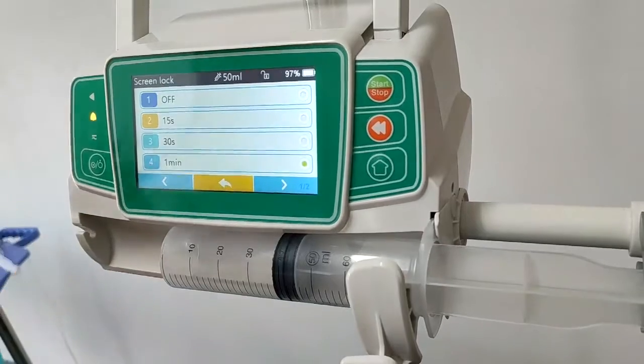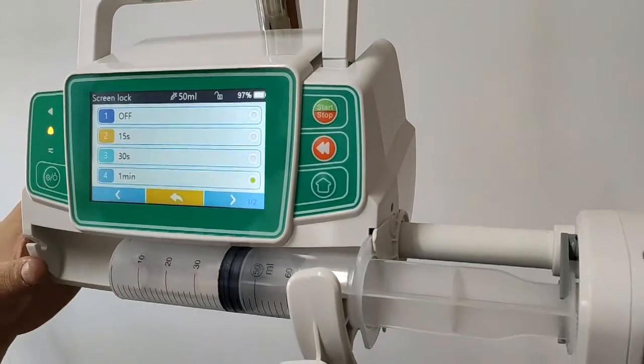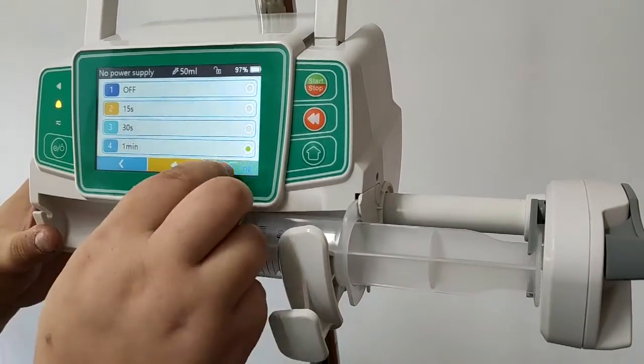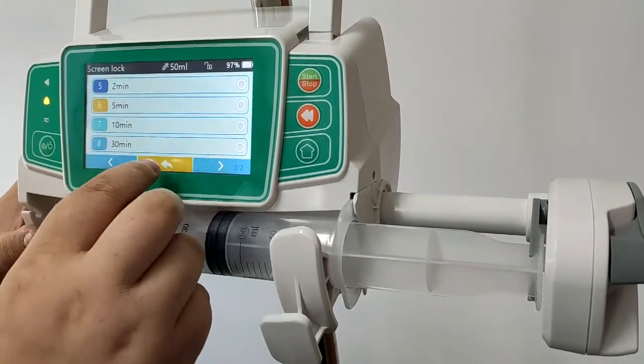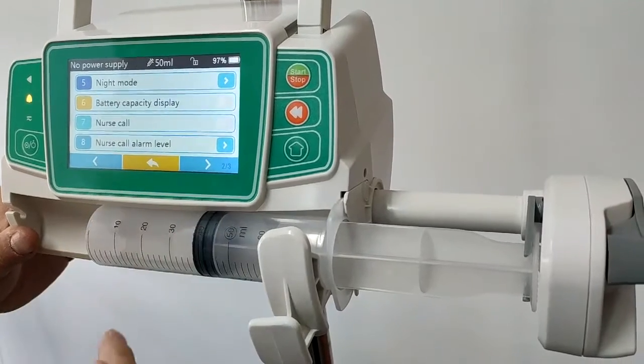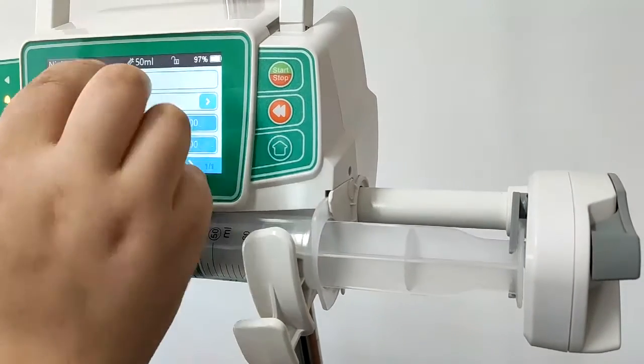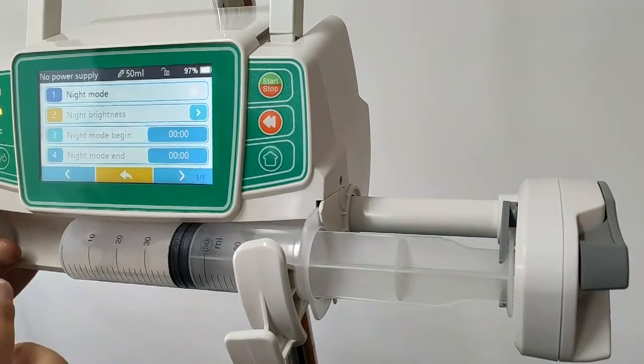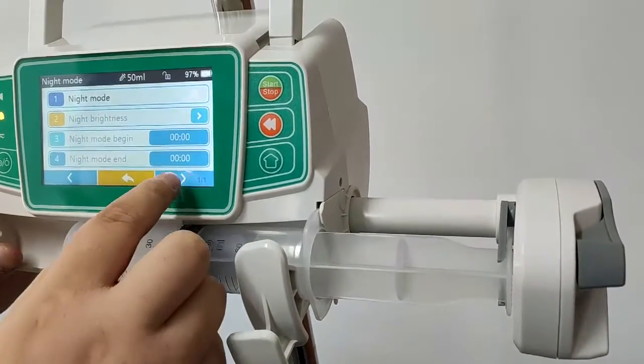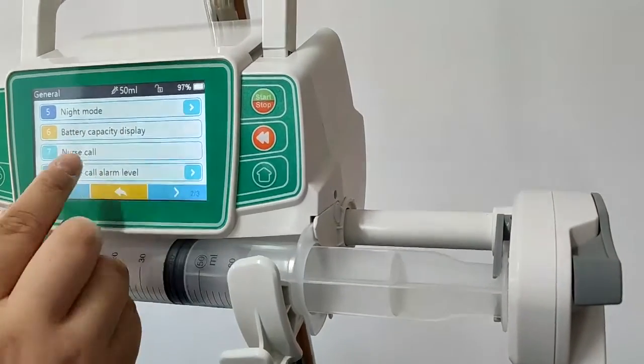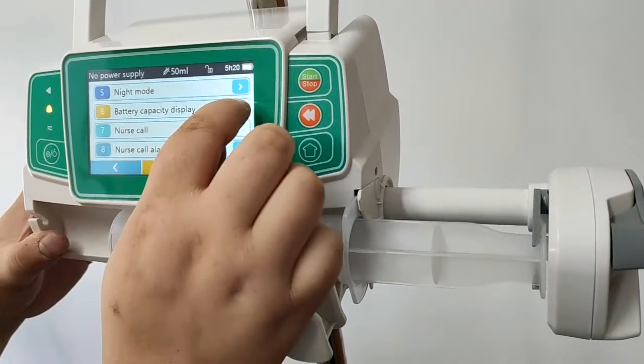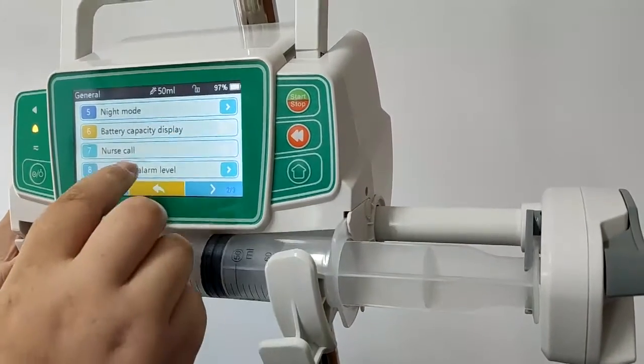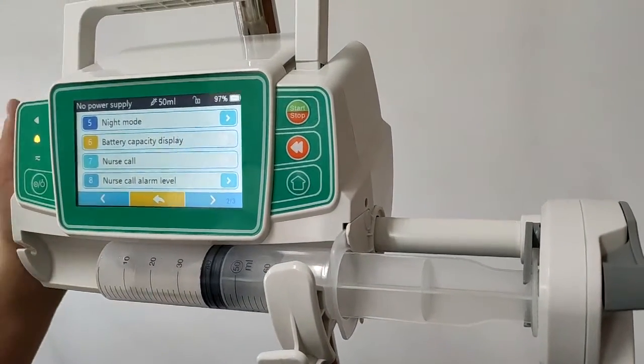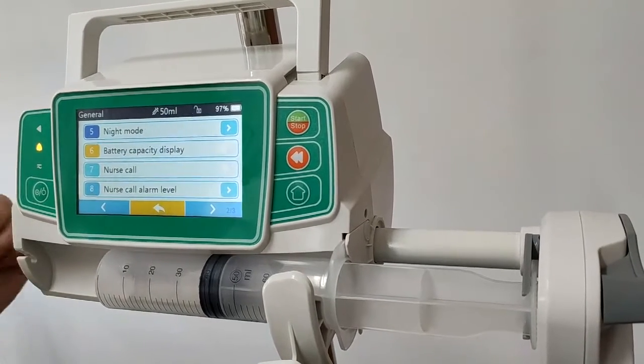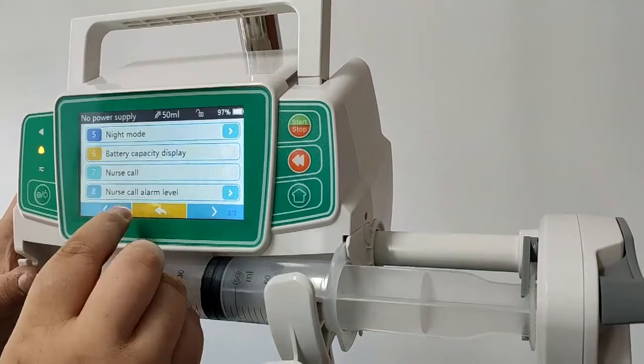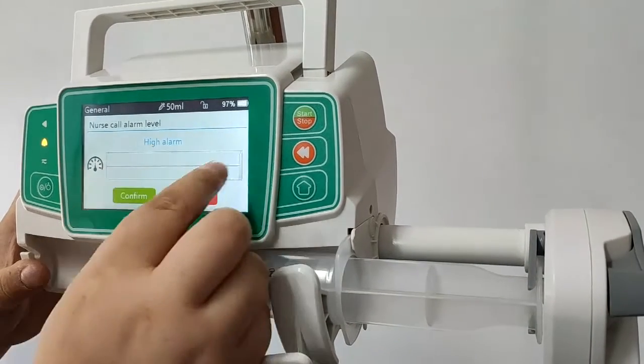And by screen lock, it means if you want the pump to be screen locked after you haven't used it from 15 seconds to 30 seconds, 30 minutes, you can just select any one you want to use. And there is a night mode by the second page. And night mode, you can set the night mode begin with, end when, and the night mode brightness. And also the battery capacity display, you can choose from how many hours left or how many percentages left. And the nurse call, you need to have an optional nurse call connection line to connect with the hospital system. And you can also set the nurse call or alarm levels to be high or medium.